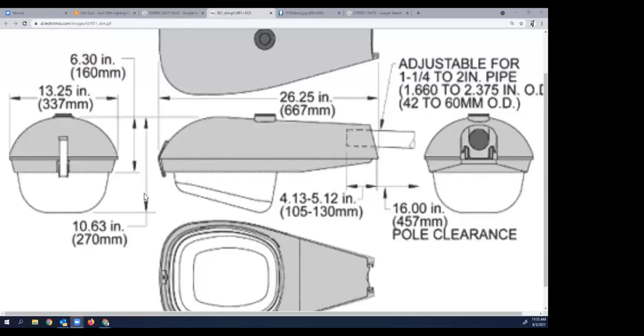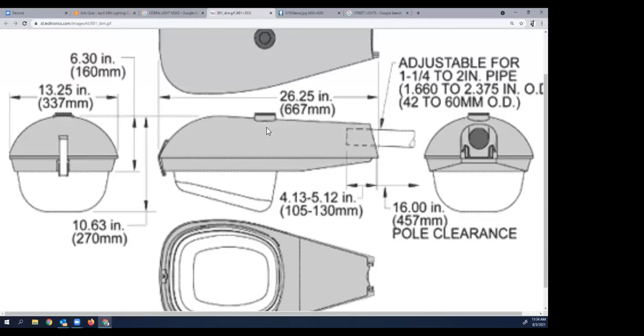Talk about what is the procedure to troubleshoot a light? And this is not concerning light pollution, but how to troubleshoot it, starting from covering the photocell, replacing the photocell, going through the lamp, replacing the lamp, replacing the ballast, checking voltage, and replacing the light fixture itself if all else fails.